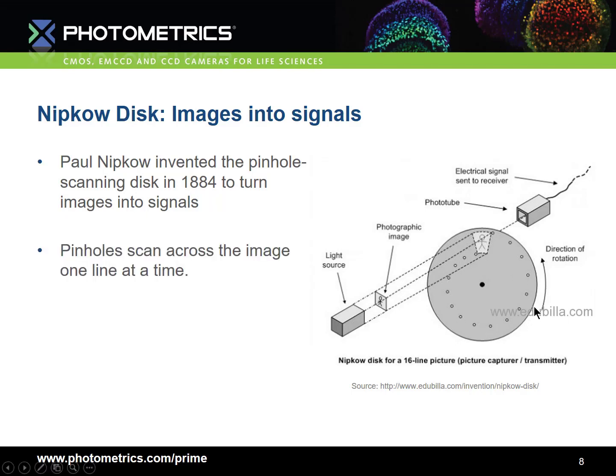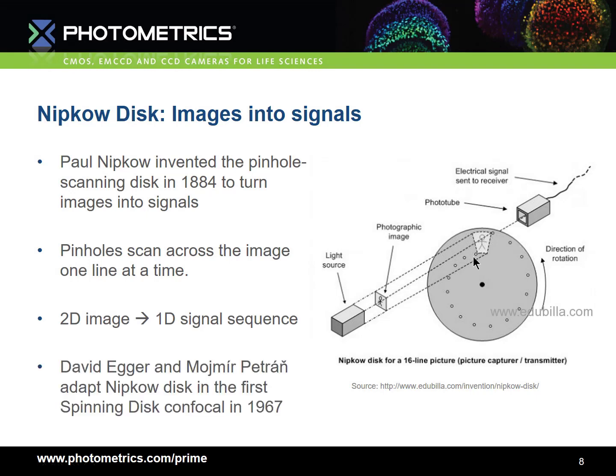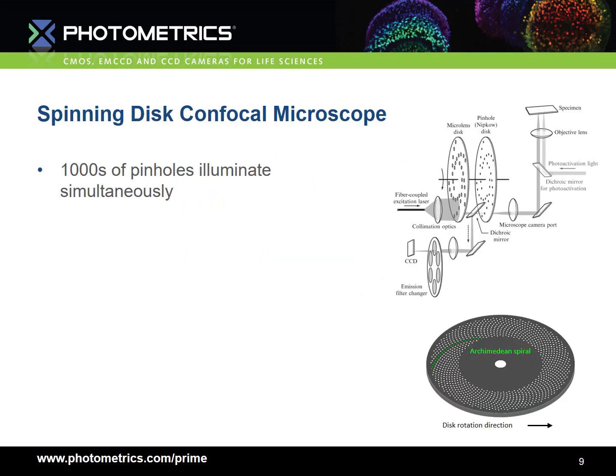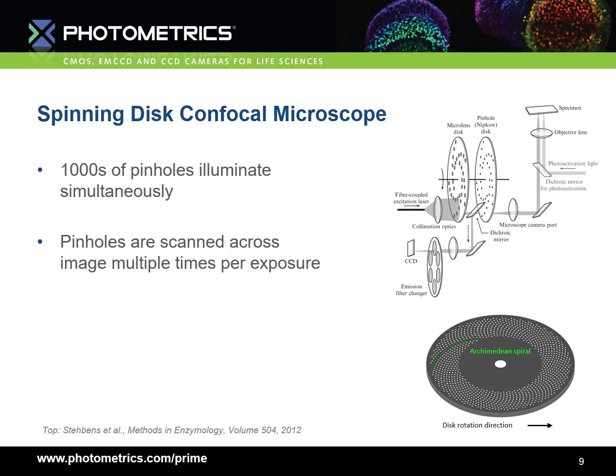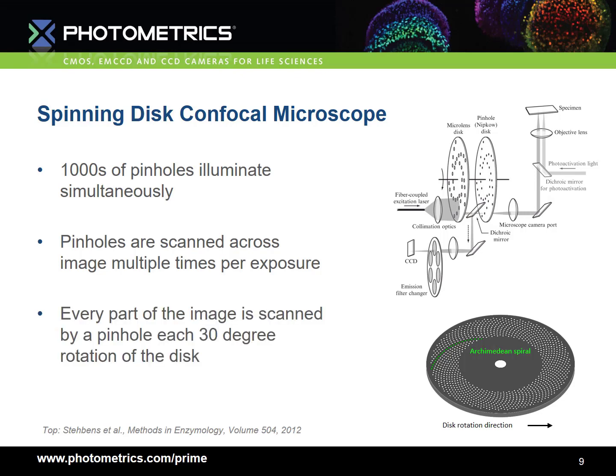Here, pinholes are arranged on a disk in an Archimedean spiral. As the disk rotates, pinholes scan across lines of the image, and the two-dimensional image is turned into a one-dimensional sequence of information. David Egger and Mojmir Petran later adapted the Nipkow disk into the first spinning disk confocal microscope in 1967. The spinning disk confocal microscope is based around the so-called Petran disk, where many Archimedean spirals are arranged on a single disk, and thousands of pinholes illuminate the sample simultaneously. These pinholes are typically scanned across the image multiple times per exposure, and every part of the image is scanned by a pinhole each 30 degree rotation of the disk.